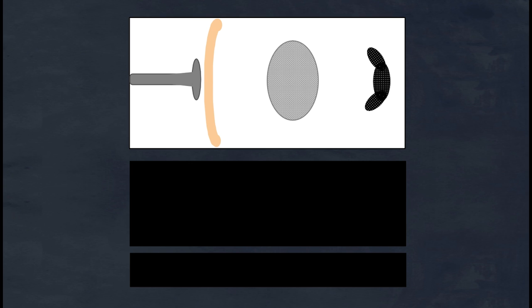Just for simplicity's sake, we are going to simulate an ultrasound by placing a little bit of gel here. Now, what is the purpose of that gel? Well, if I don't have that gel, then we have the acoustic impedance from air going into skin. The difference is so great that most of the sound is reflected, which means you get no transmission of any sound. So the whole purpose of the gel is to have a similar acoustic impedance to the skin, so that we have maximum transmission of sound through.